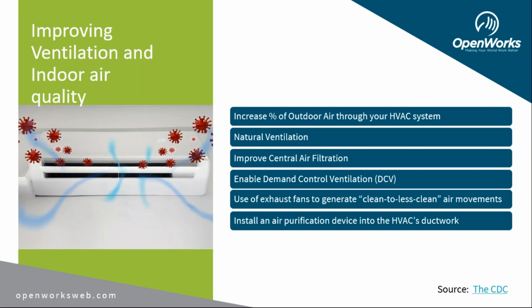Here we have strategies for improving the ventilation and indoor air quality of your buildings. You can do things such as increase the percentage of outdoor air through your HVAC system. This can be accomplished by opening those fresh air dampers to a higher operating percentage, or you can program your economizers, if you have them, to bring in more fresh air. We can consider using natural ventilation, such as opening doors or windows if it's safe to do so. This again will help to dilute the stagnant indoor air with fresh outside air. However, this only makes sense if the conditions outside are optimal and it is allowed at your building.